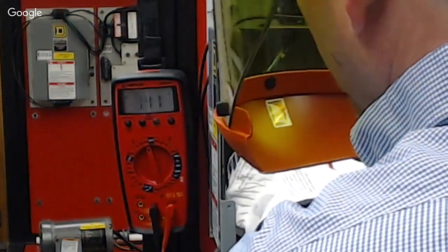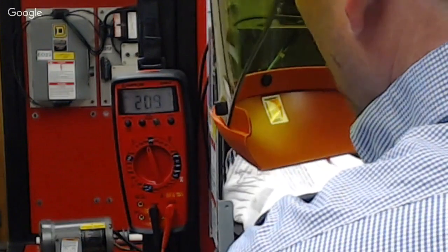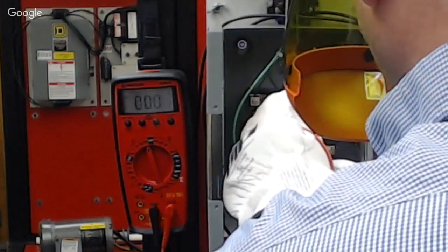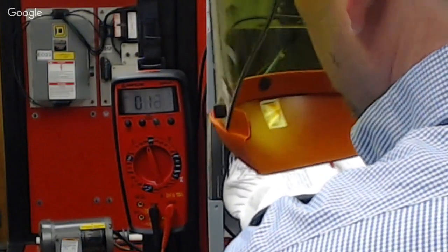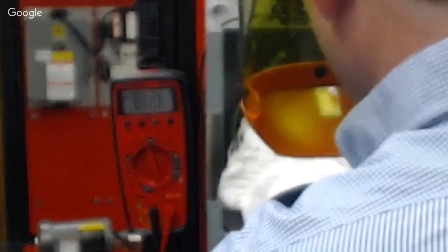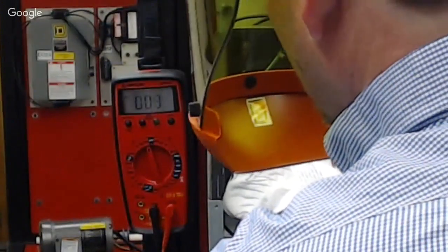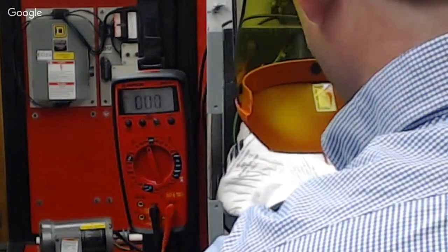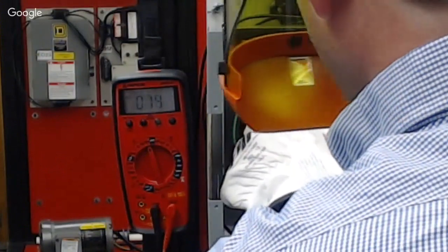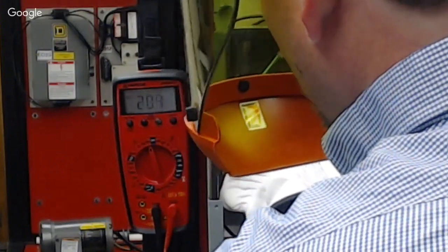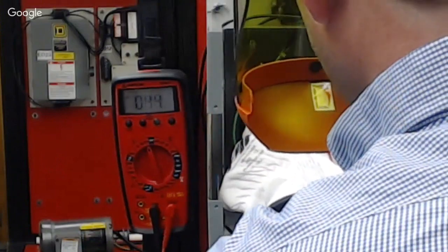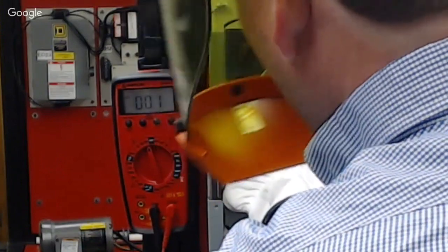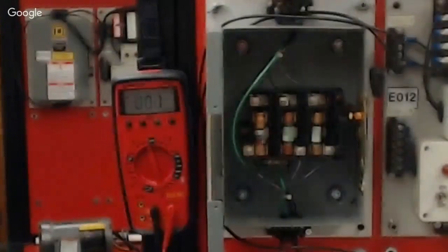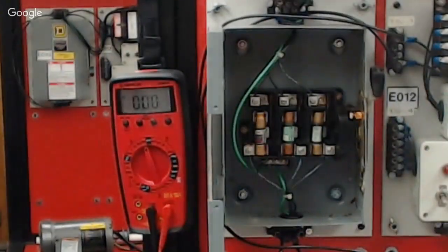Here we go. So now we're reading 220 volts, or 208 because it's three-phase, and we're going to check from here to here, and no, we're not reading anything right through here. So I'll check up here. I'm reading 208, but if I go down here, there's no continuity for a path to flow, so I'm not reading anything. So I know that fuse is bad, but I can double check that by pulling it out.